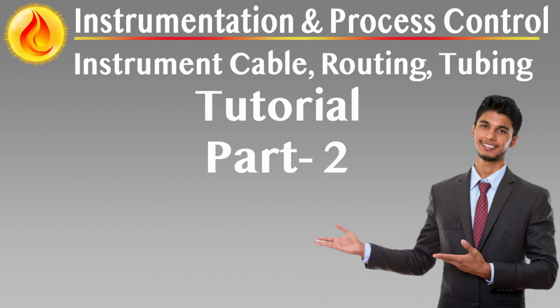Where power or lighting cables intersect signal lines, crossings must be made at right angles with a minimum separation of 0.3 meters to mitigate electromagnetic coupling. Trenches must also avoid proximity to buried hot surfaces, such as uninsulated process piping. A minimum separation distance of 0.2 meters plus 0.1 meters per 100 degrees Celsius of pipe surface temperature is required to prevent thermal insulation degradation. The trench bottom must be leveled and limited to a slope not exceeding 10 degrees. Sharp directional changes must include smooth radii to comply with minimum cable bend tolerances.